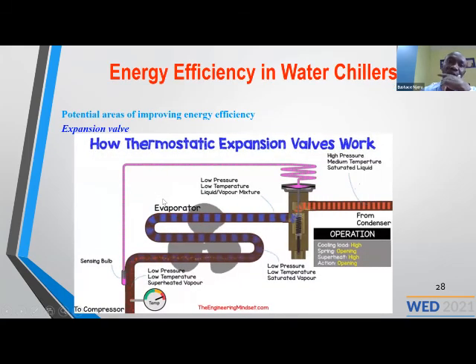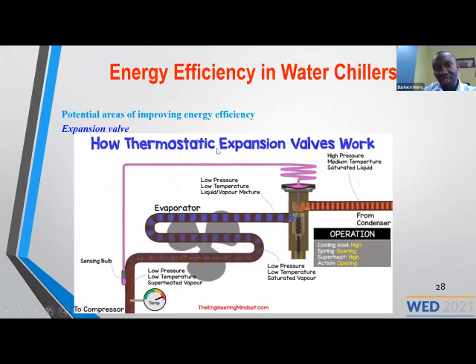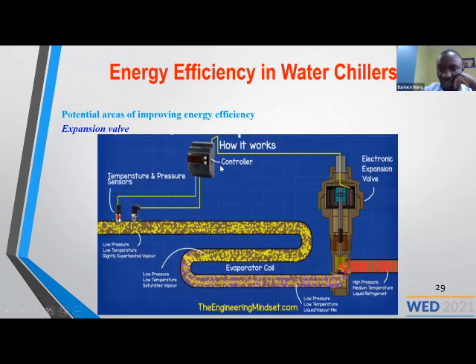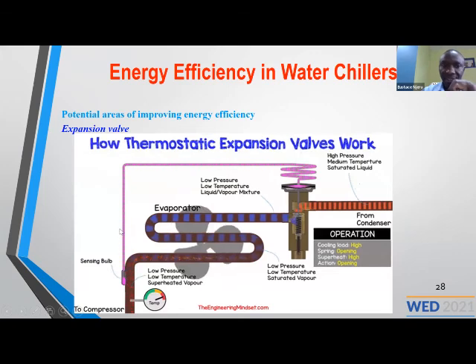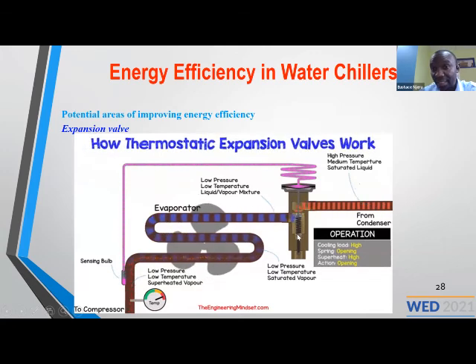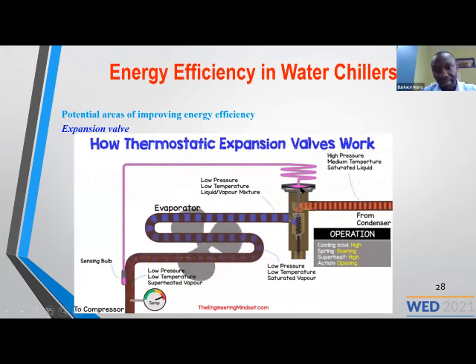The other one is the change of expansion valves we talked about. Instead of using thermal expansion valves, you can use electronic valves. This shows how the thermal expansion valves operate. It uses a volatile fluid, almost similar to the refrigerant. You can see, for you to operate the thermal expansion valve, this fluid needs to expand and push the diaphragm down so that it can allow more refrigerant to the evaporator and to the compressor. So after getting what we call the superheating, the level of superheating after the evaporator, this fluid gets heated and it pushes the diaphragm. So you can see its sensitivity is a bit different compared to that of the electrical systems. An electrical signal moves faster than the expansion because it's more mechanical.